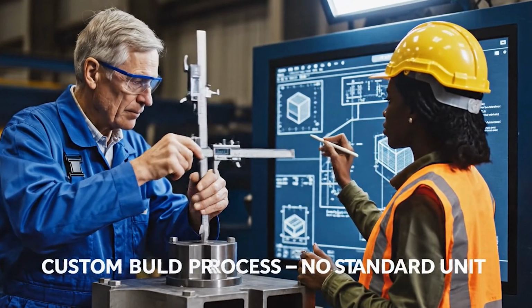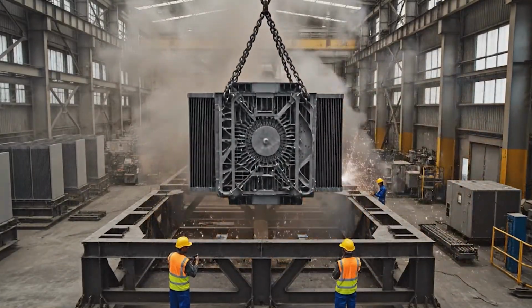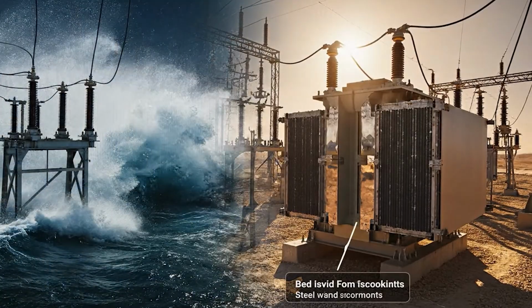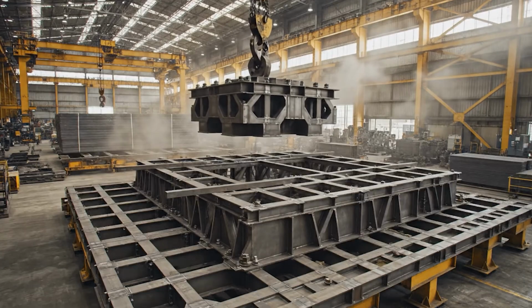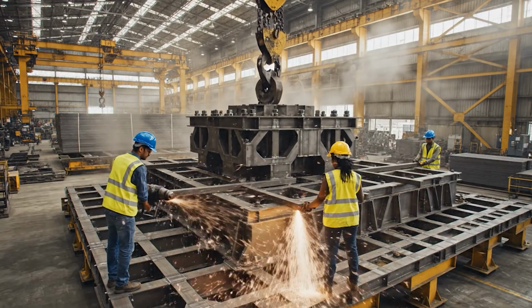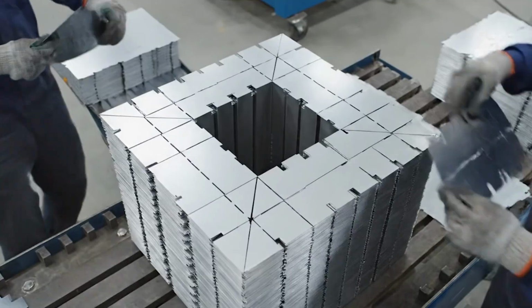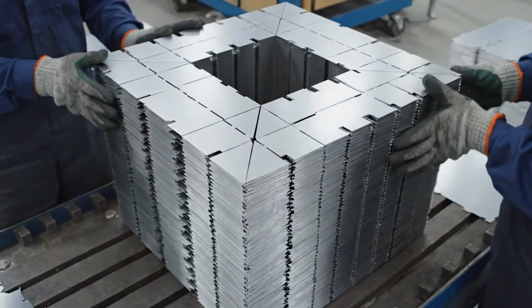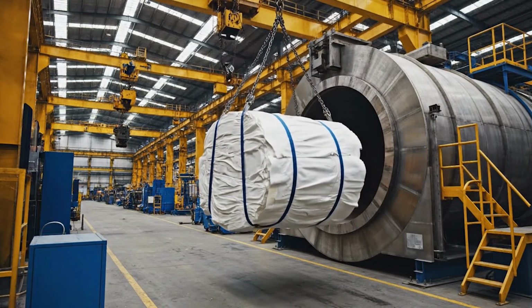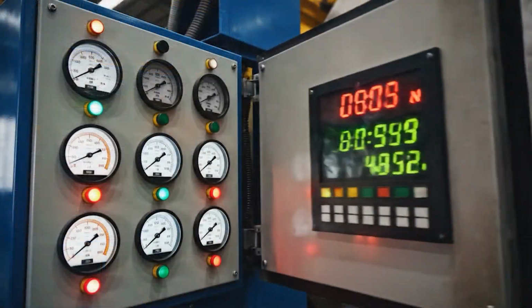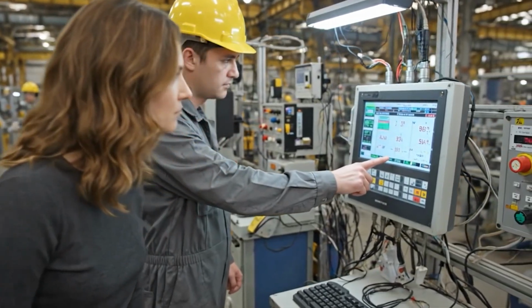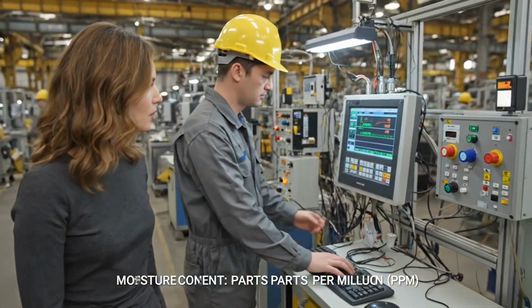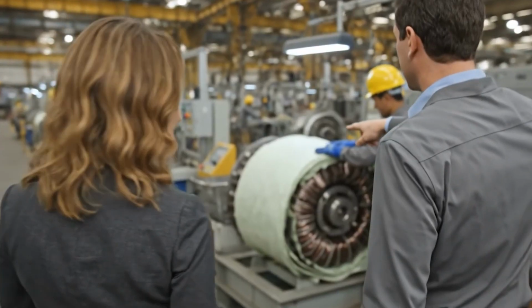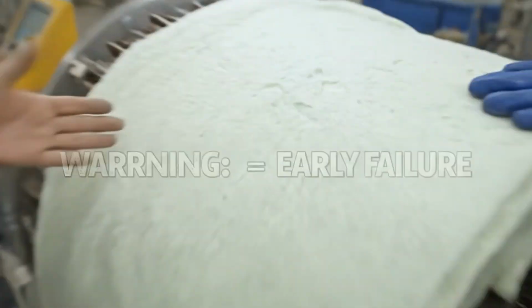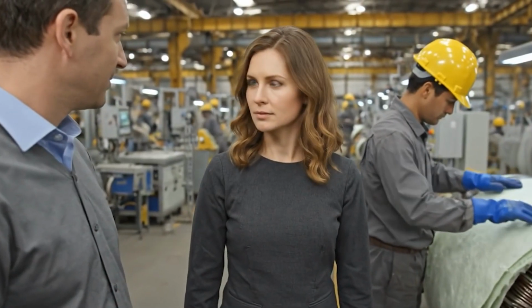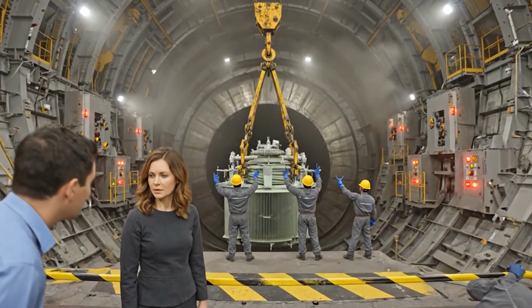Here's why these machines take so long. Every large transformer is custom built, designed for a specific substation, a specific voltage, a specific climate. The steel core is assembled from thousands of thin laminations, each one cut precisely, stacked by hand in many cases. The copper windings are wrapped with exact tension, insulated with special paper. Then the whole assembly is dried in a vacuum oven for days. One engineer told me they measure moisture content in parts per million. If the insulation is even slightly damp, the transformer will fail early. So they bake it.